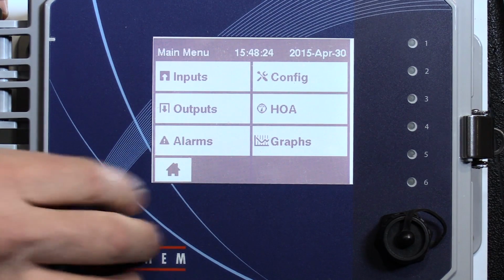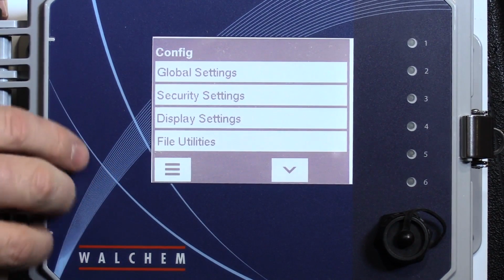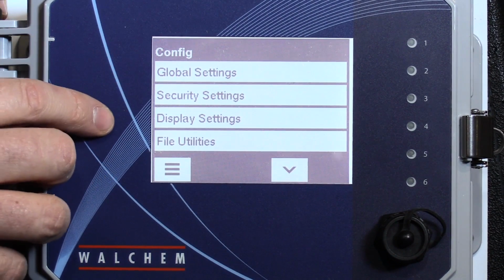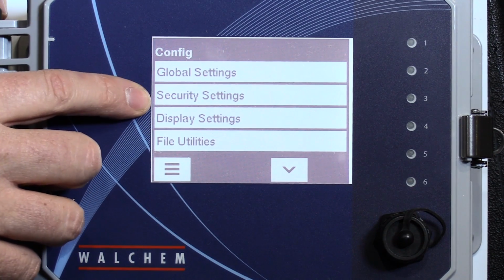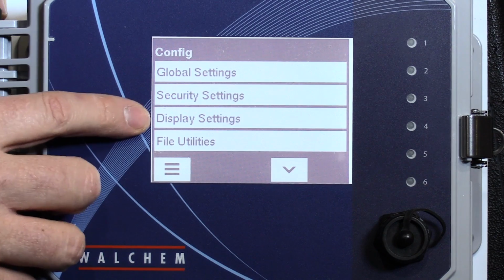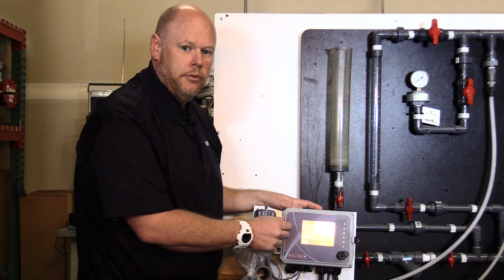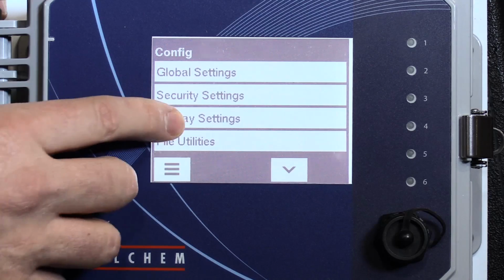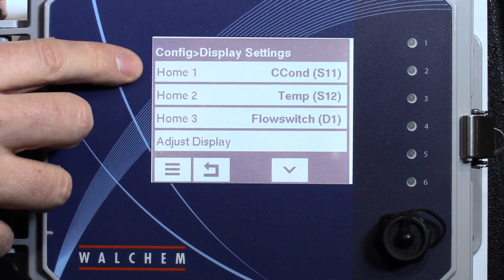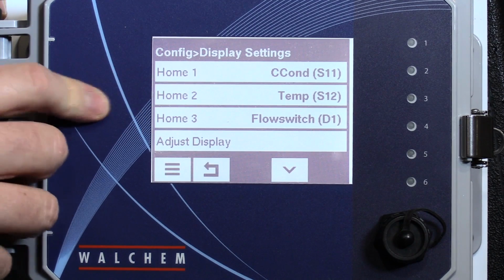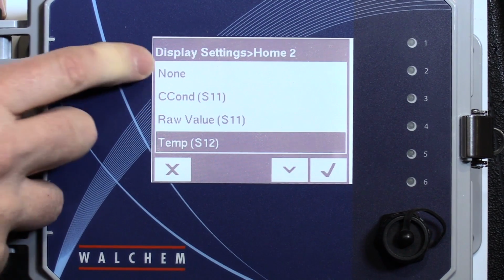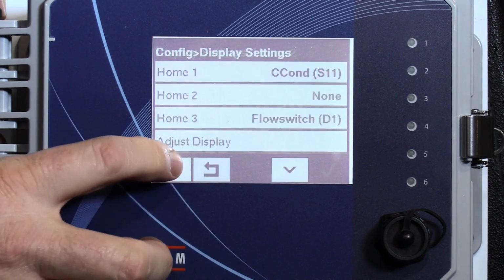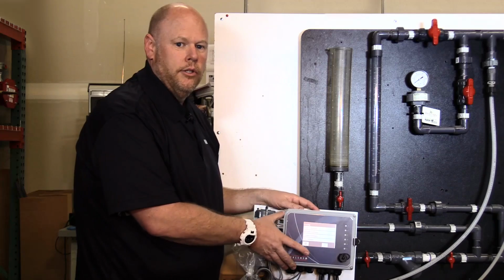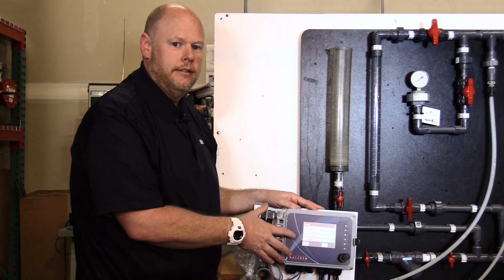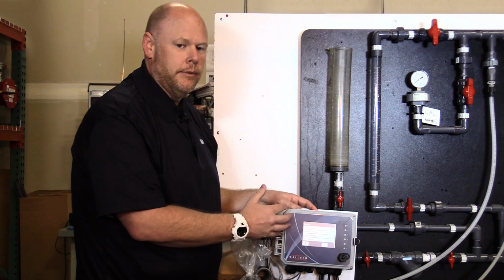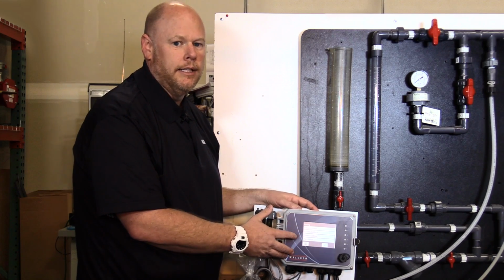Lastly, you have your config file. That is for your global settings, which would be your day and time, your security setup if you want to put a password on the controller, your display settings to show what sensors you want, temperature, conductivity. If you would like to have the conductivity on, the temp on, the flow switch. If you're not using your temperature, you can turn it off, select none, accept it, and go back to the main menu. Once this controller is programmed, you can export the file and you could upload it to any existing W600 controller so you don't have to program them again.